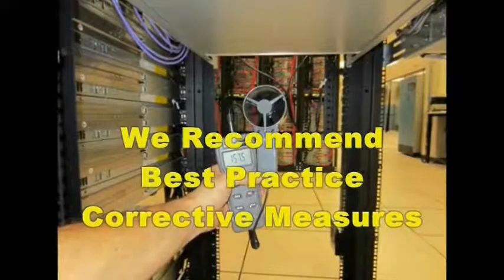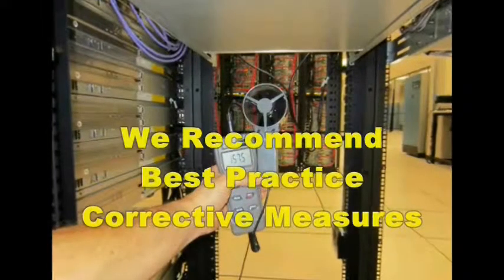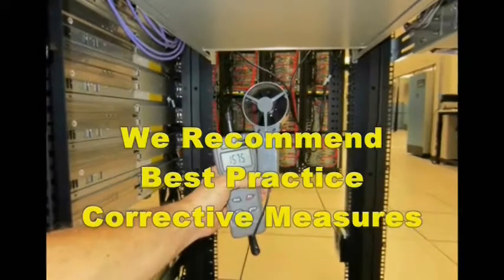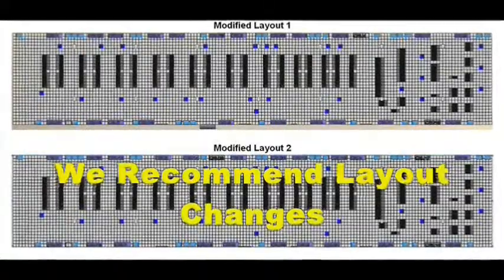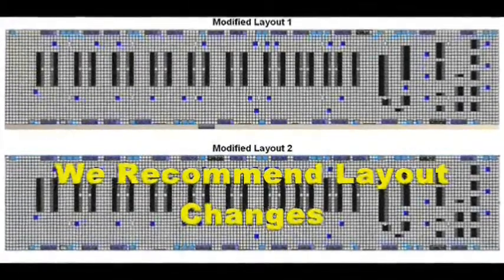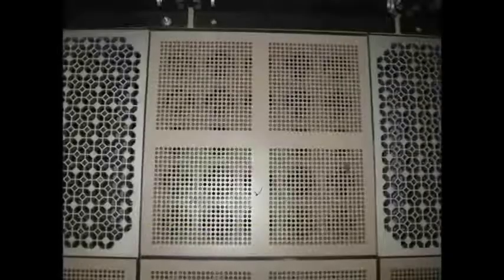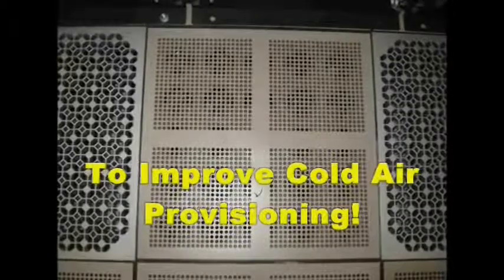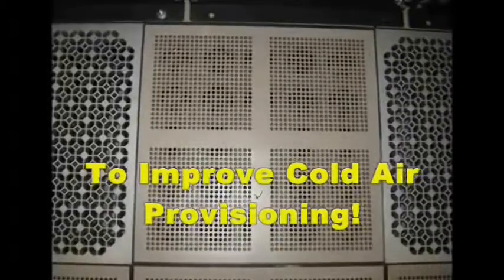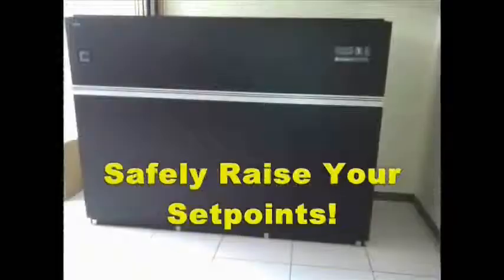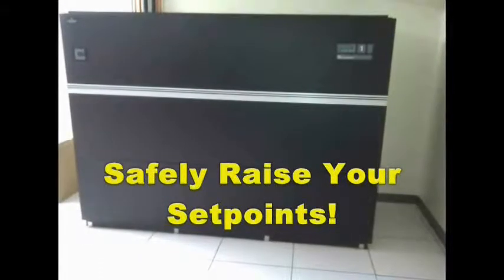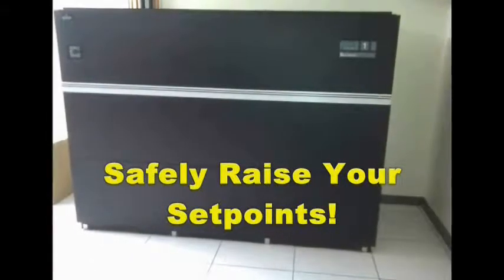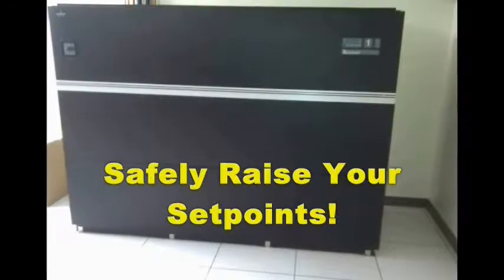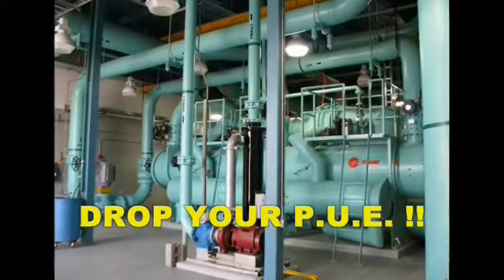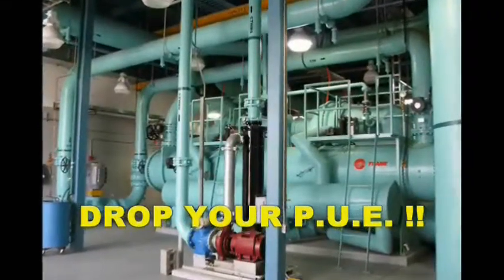We recommend best practice corrective measures, the low-hanging fruit of energy efficiency gains. We engineer specialized perforated tile and CRAC unit layouts to help you optimize the supply and return paths of cooling air. Ultimately, we help you achieve an equipment layout that will allow safely raised temperature set points in the data center. This is the key step to enhancing your efficiency or driving down your power usage effectiveness number, PUE.